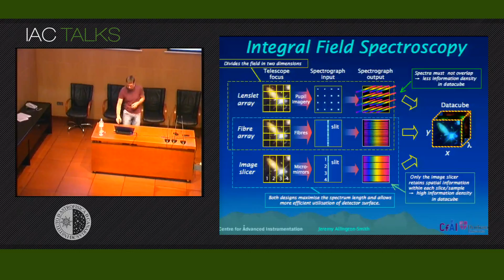So how does it actually work for MUSE? As I said, you need 24 CCDs to record all the information with the sampling that you want. So there are actually two steps involved in dividing up the field of view. If you observe a galaxy like this, which in reality is actually much too big to fit in the MUSE field of view. Anyway, if you want to observe a galaxy like this, you first split up the field of view, not into 4 subunits, but into 24 subunits. And each of these subunits is then fed from the field splitter onto the image slicer, which is this here. It's also called the image dissector array, IDA, and then onto this focus mirror array here, which then feeds the light into some kind of pseudo slit, which is then going through the spectrograph in the end.